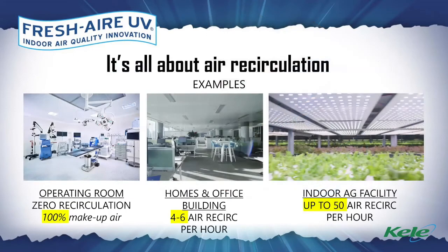And that's, again, where we want to understand the application. So if we're looking at a hospital, and you contact me and say, Aaron, I've got a facility. We want to put UV lights to address airborne viral contaminants. It's an operating room. Well, chances are the hospital is bringing in 100% makeup air. And as I mentioned earlier, I talked about sunburns, how one sunburn won't be an issue for anybody, but continually abusing the sun with enough sunburns over the course of their life will eventually lead to a mutation, which presents itself as skin cancer. Well, for a hospital, we don't have that second, third, fourth sunburn. We don't enjoy the ability for the accumulation of a dosage. We have to deliver that lethal dosage on one pass.